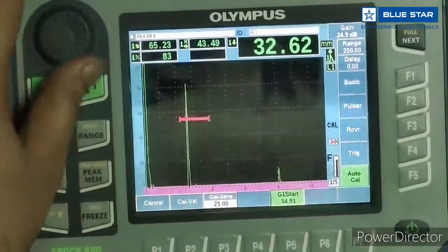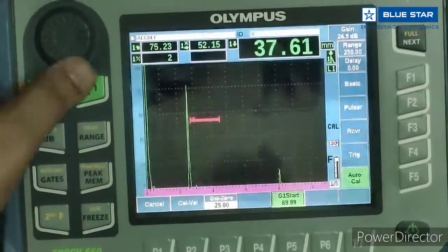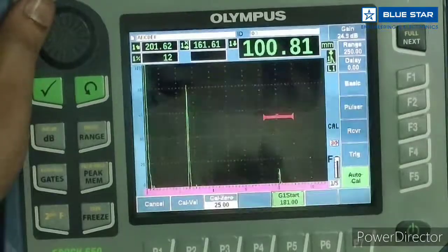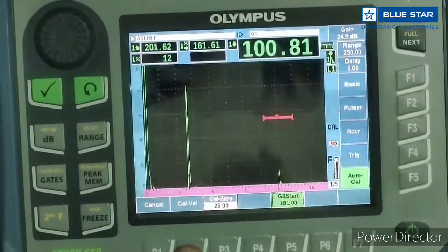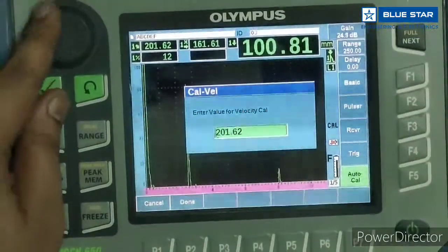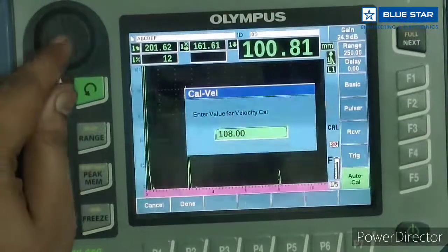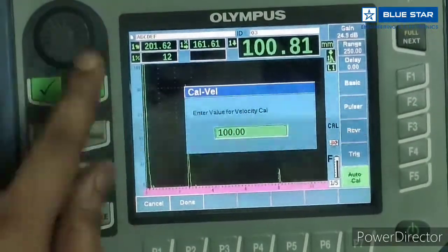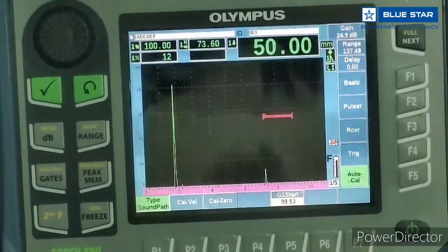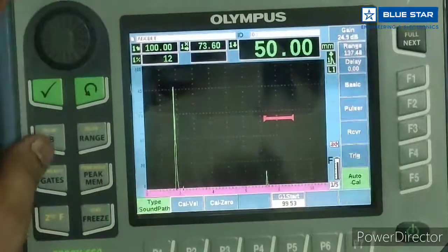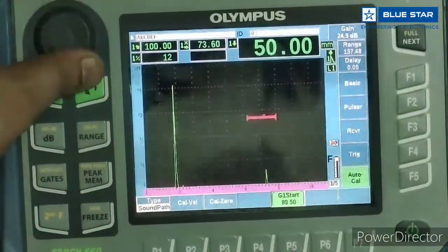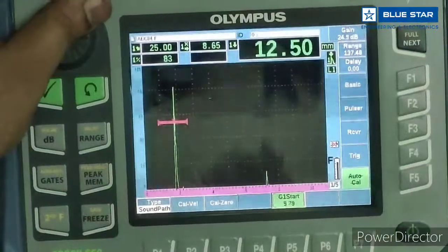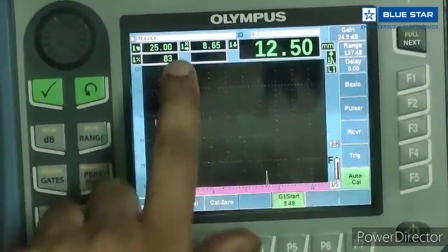And again press gate start, G1 start and move the gate to second indication. On second backwall, press Cal-Vel, enter the value 100 mm. The second backwall on V2 block is 100 mm and press done. Now shift gate and verify your beam path. Beam path is showing on top left corner.